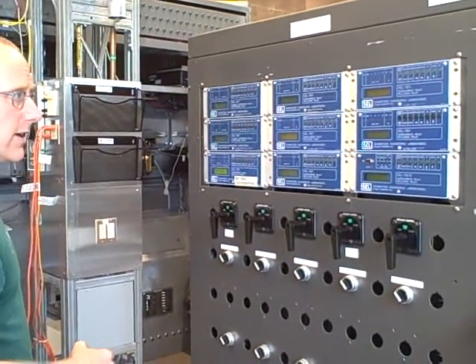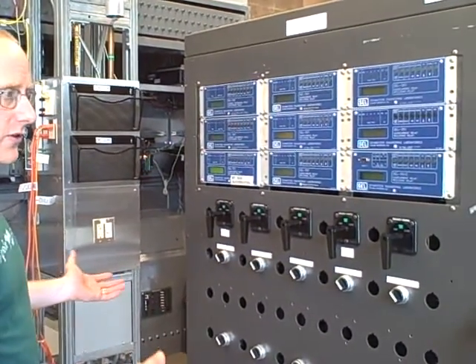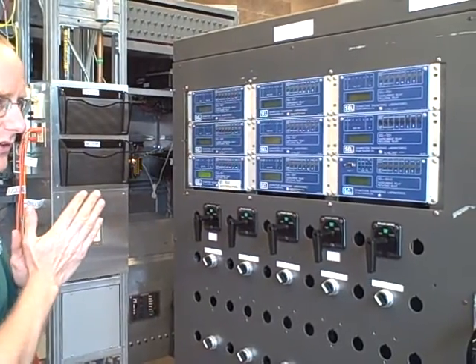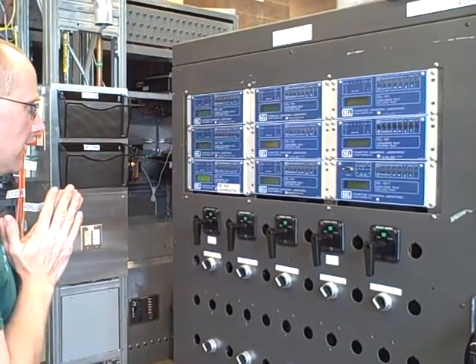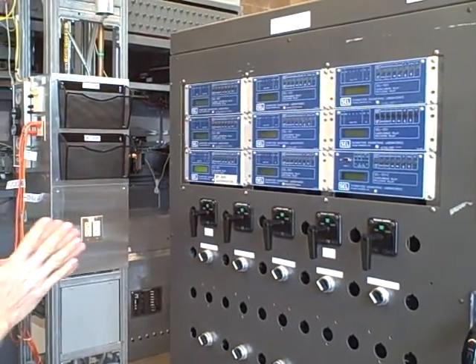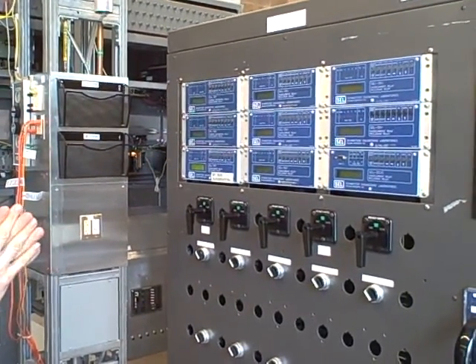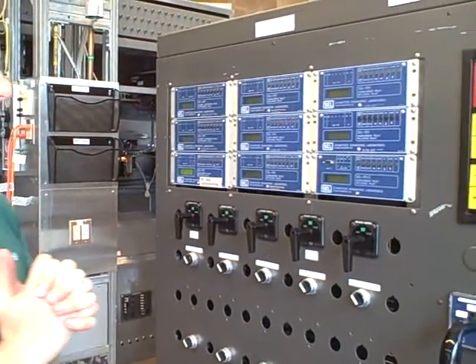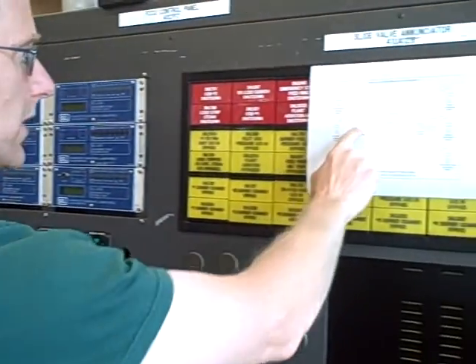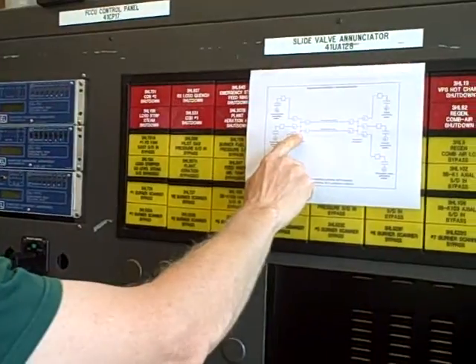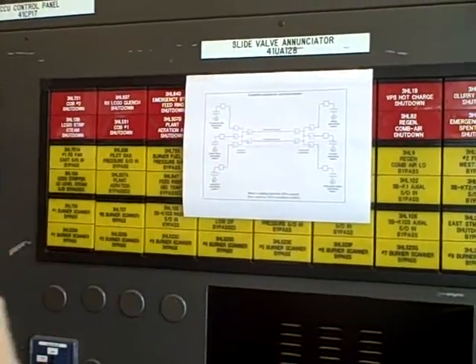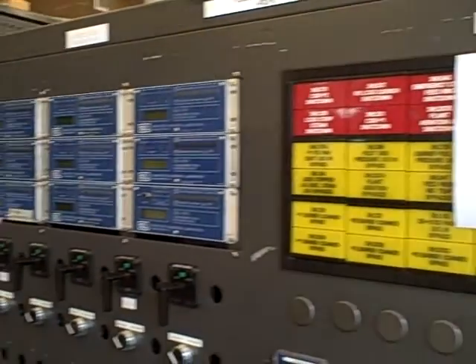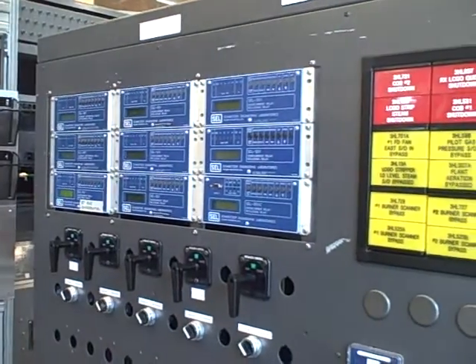We are here with our substation in our miniature AC power grid system at BTC's instrumentation lab. We want to demonstrate a different sort of fault on the system. In one of the other videos we showed a fault on the bus of our substation — an internal bus fault — and we demonstrated how the 87 relay would detect that fault and trip the breakers.